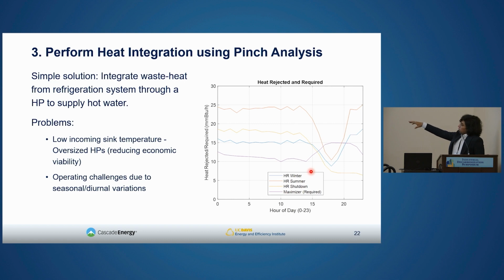For example, the blue is heat rejected in the winter, the yellow is heat rejected during shutdown, whereas the red one is heat rejected during summer operating modes. So here we can see that the plant is rejecting more heat than it is using to heat up its hot water. But this is a low temperature heat, so we cannot do direct heat exchange. But there's an opportunity to use a heat pump where we can extract all of that waste heat and use it to supply high temperature heat to our hot water. We call this a simple solution, using just a simple heat pump for this process.